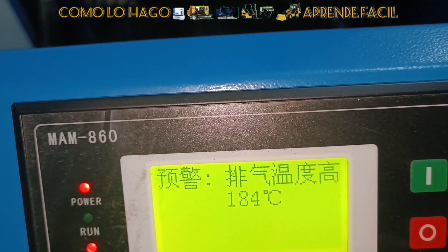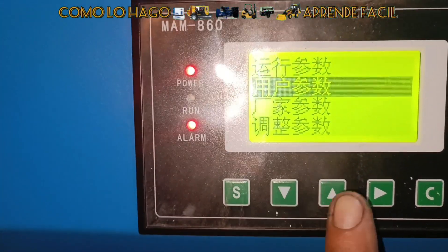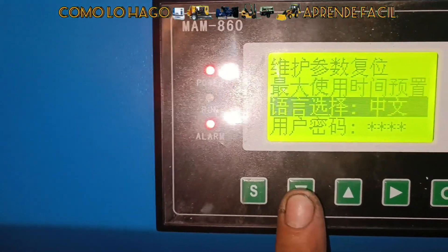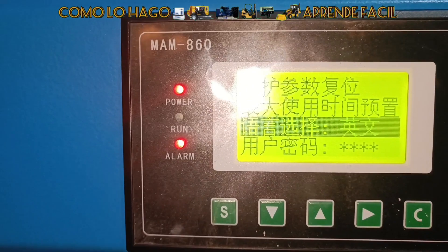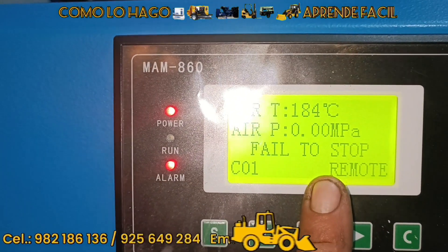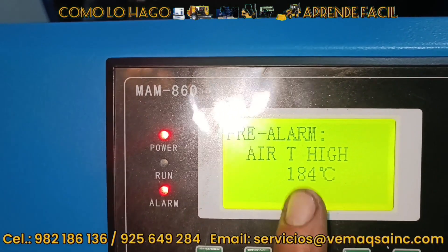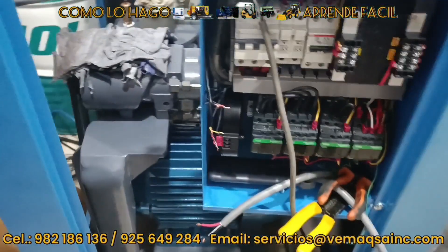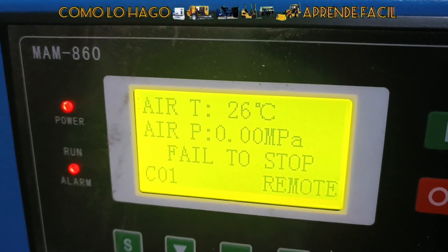Ya tenemos voltaje en la línea. Activo inmediatamente el panel. Nos debe estar saliendo advertencia por temperatura — correcto, 184 grados, dice eso porque está desconectado el sensor. Estamos ahorita en chino, lo que vamos a hacer es cambiarlo al español o en todo caso al inglés. Estos equipos vienen con varias opciones de idioma. Dice presión 0 y temperatura 185 grados porque está desconectado el sensor. Vamos a conectarlo — ya conectamos el sensor y continúa sonando la alarma. Nos está registrando 26 grados, que es la temperatura ambiente ahora. Presión 0.